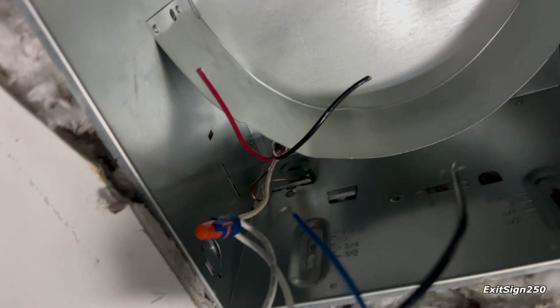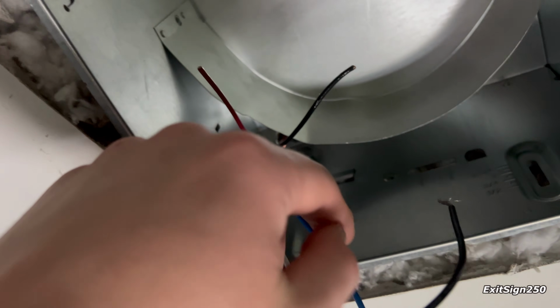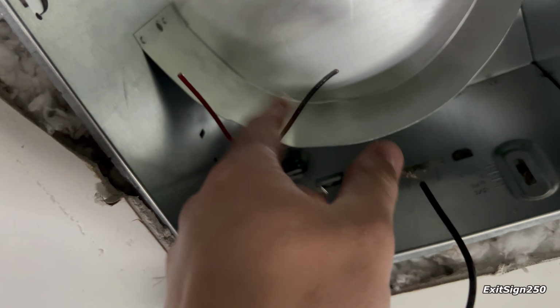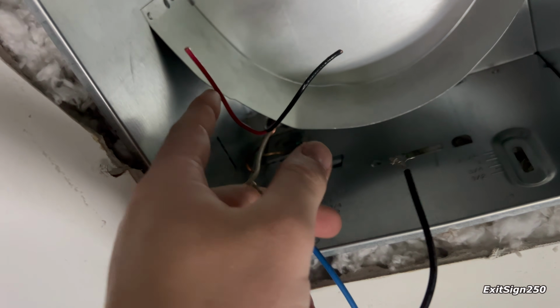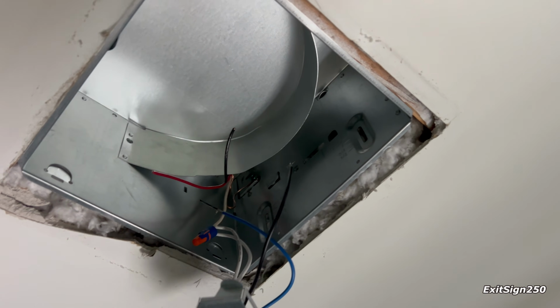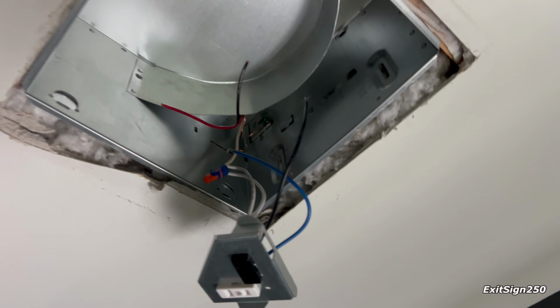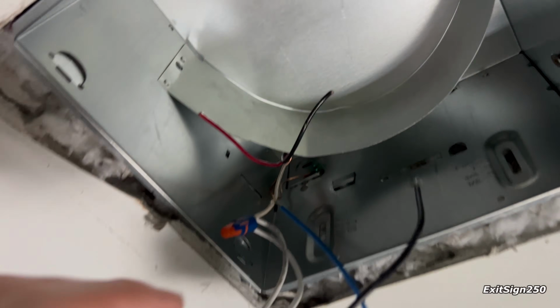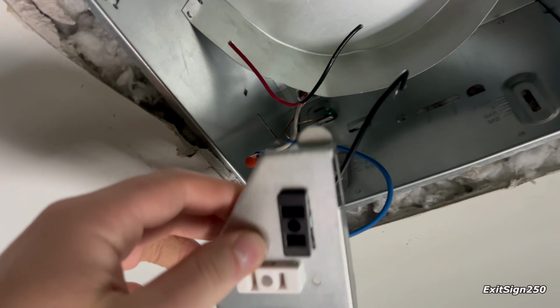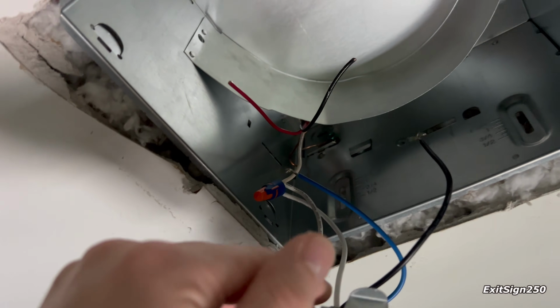As far as the wires that are coming in here, there's a black and a red. Traditionally, the black wire is the fan and the red wire is the light. That goes for both exhaust fans and ceiling fans, but I have seen it the other way around, so normally I just check to make sure which wire is doing what.